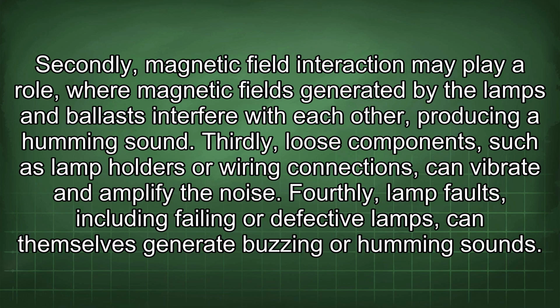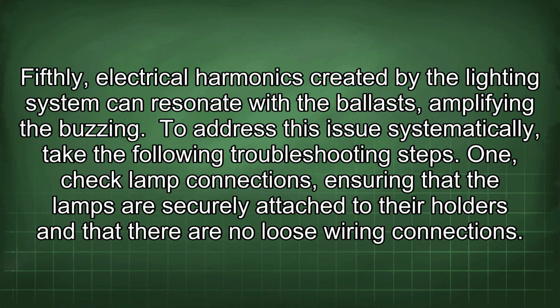Thirdly, loose components, such as lamp holders or wiring connections, can vibrate and amplify the noise. Fourthly, lamp faults, including failing or defective lamps, can themselves generate buzzing or humming sounds. Fifthly, electrical harmonics created by the lighting system can resonate with the ballast, amplifying the buzzing.